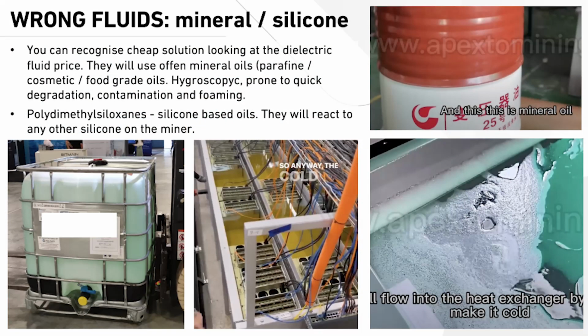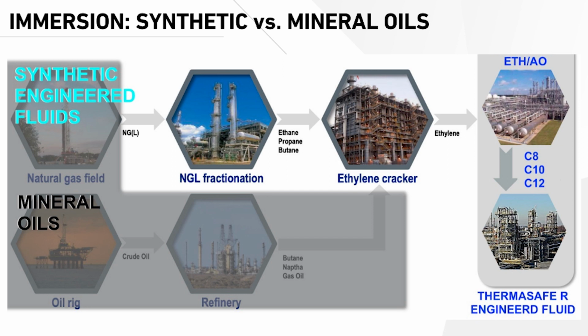Choosing the wrong fluid, like mineral oil instead of synthetic oil, is another issue. Mineral oil ages so much faster, so that's a pretty important consideration. It will decide between operation working great for a decade versus operation on degraded fluid after just one year. It's happening big time. There's a huge difference in quality and operational standards between synthetic oils, even ones branded as immersion cooling oils, fully synthetic oils, and mineral oils.